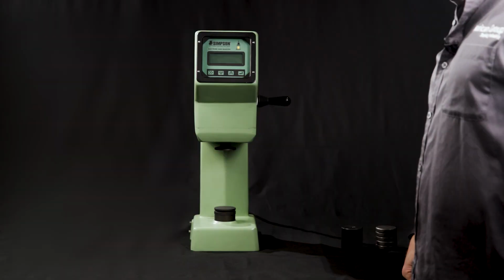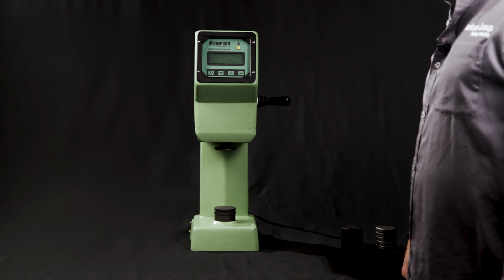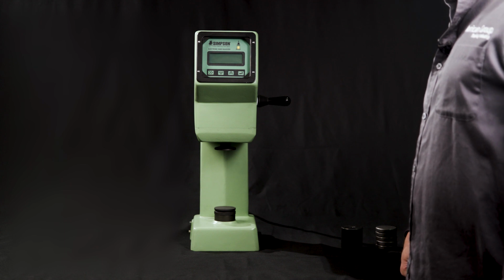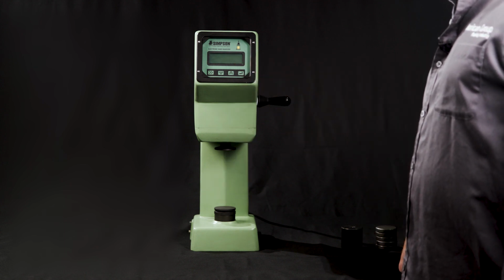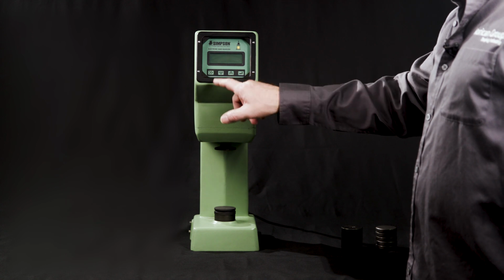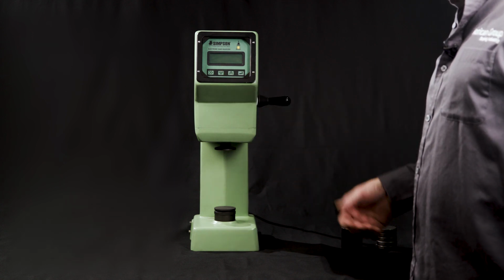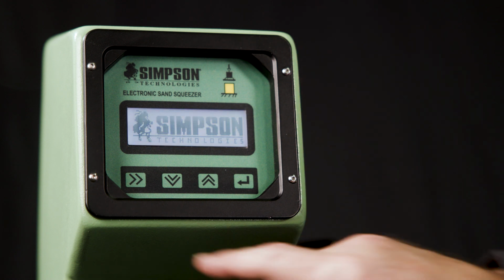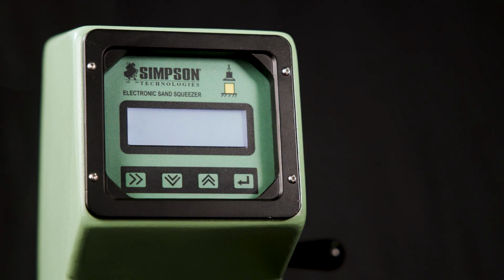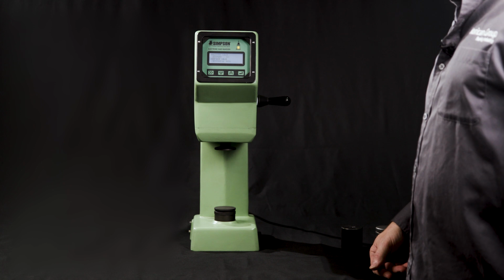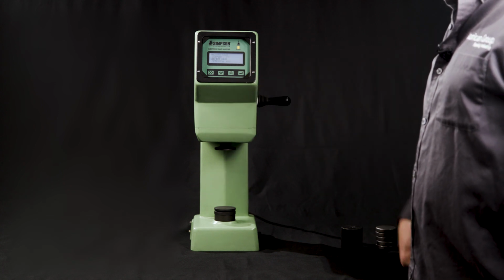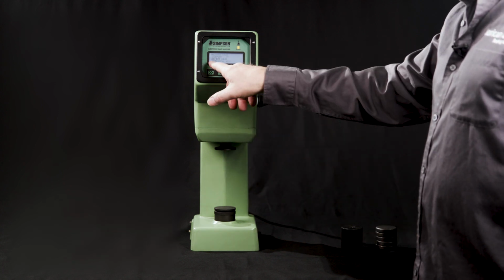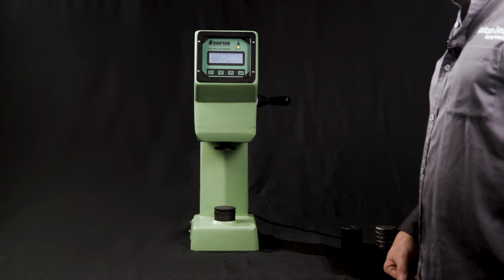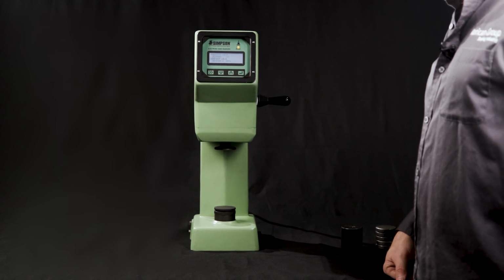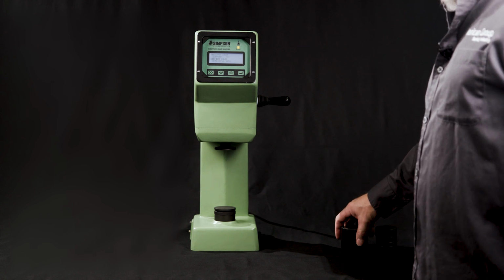We're going to go into the calibration mode of the electronic sand squeezer, pressure and the vertical displacement calibration. We're going to turn on the power. Simpson logo is going to come up on the display. At that point, we're going to press this button once and this button 3 times quickly while the Simpson logo is up. And we'll go into the calibration mode. At this point, you will see the pressure calibration, vertical displacement calibration, and there's a cursor that will be blinking on and off that indicates which calibration mode you're going to do first. Vertical displacement comes up first.